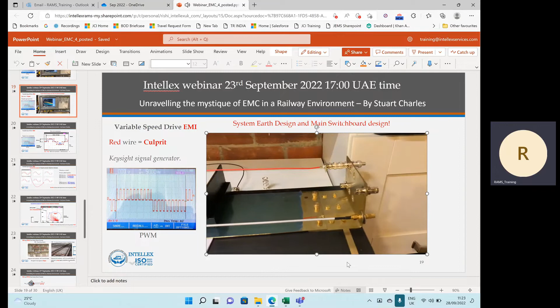Now in the real world, your drive, your VSD output, the 3-phase motor, will probably be 3-core cable with steel wire armor. But the key thing is the SWA must be terminated at both ends, otherwise we will not gain this reduction in external noise. That's not the whole story - we yet have to talk about filters, because we can still be contaminating the mains, dependent on whether the VSD has an input filter with its 3-phase 50 Hz supply, and how we design our AC switchgear. That's in another section.